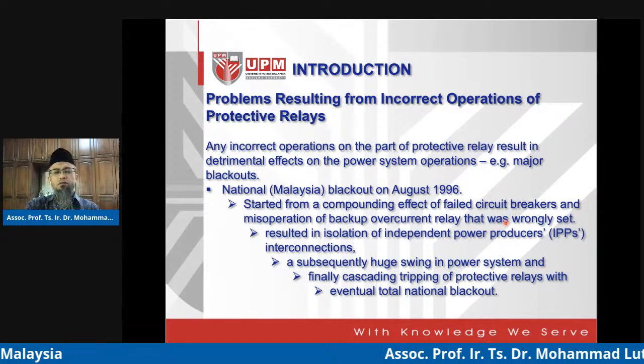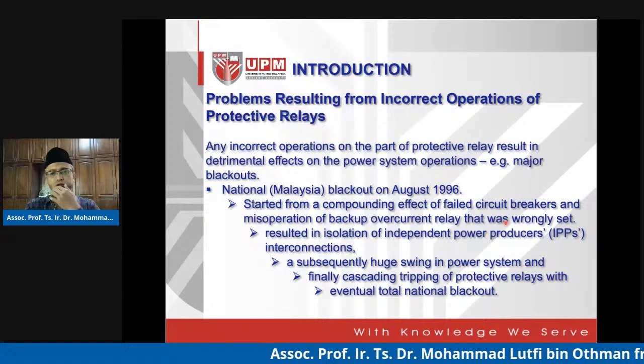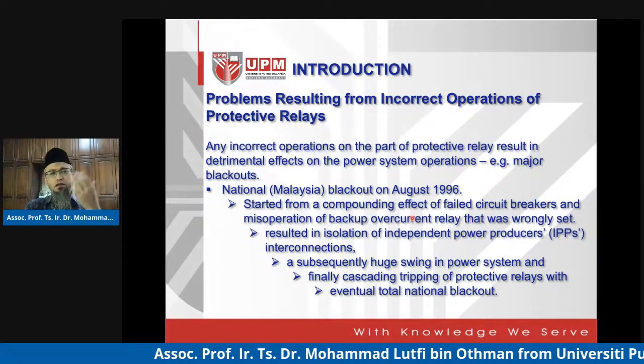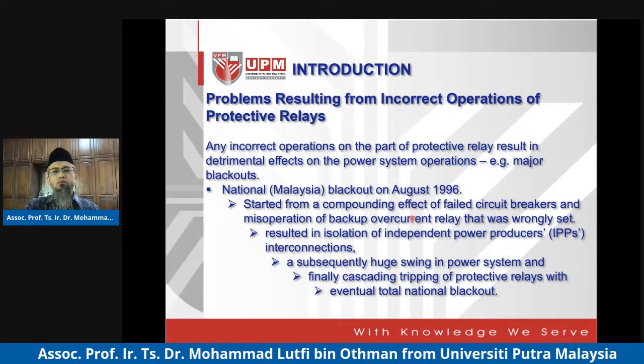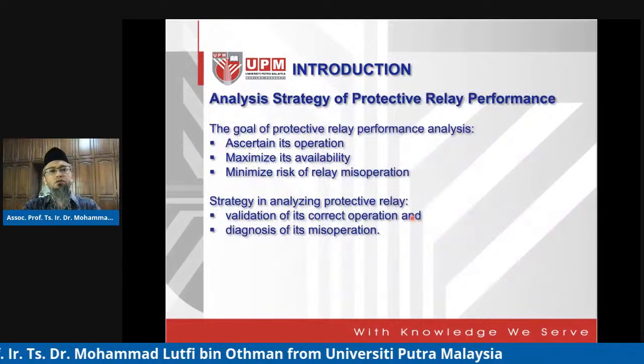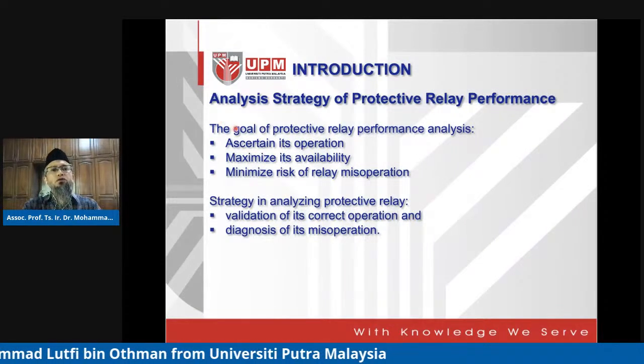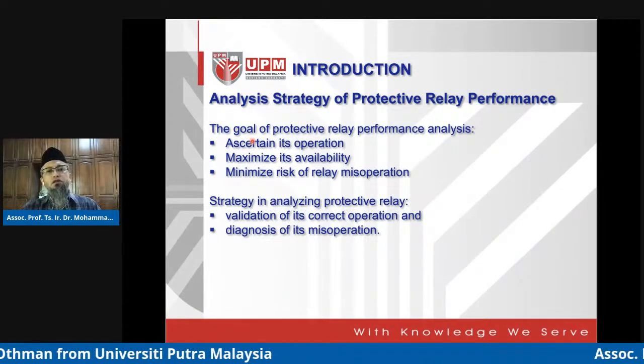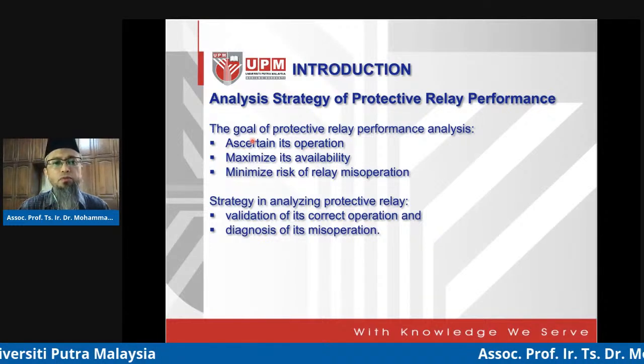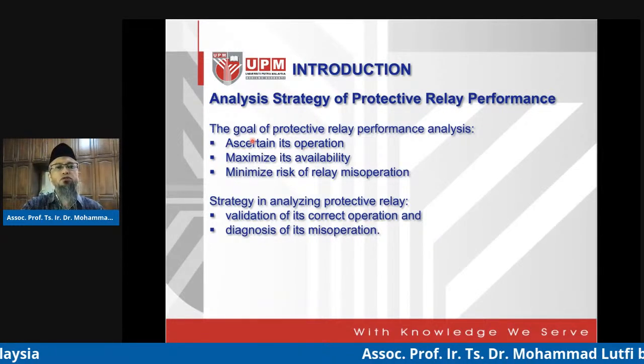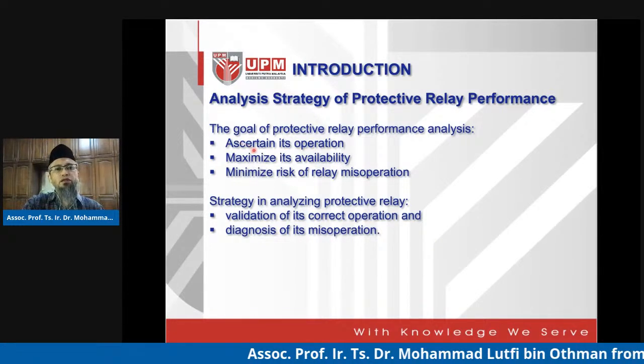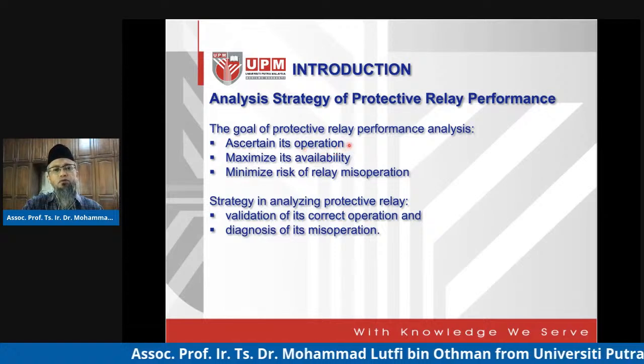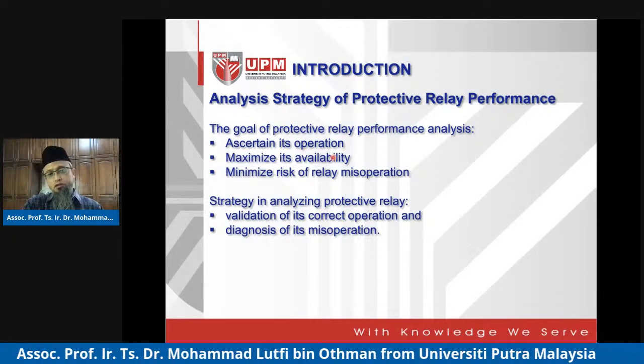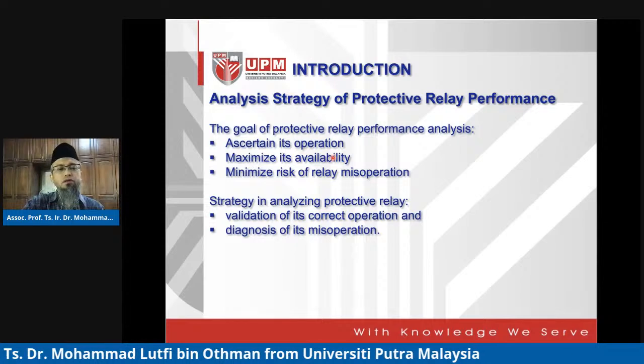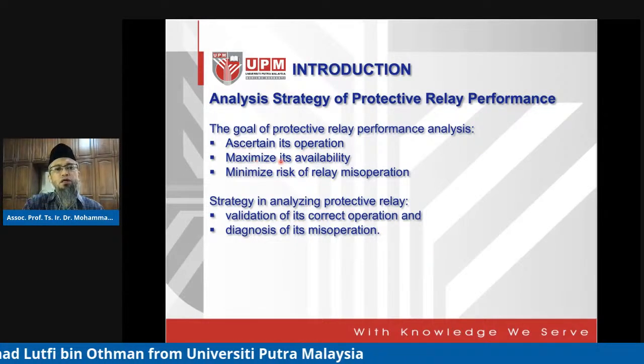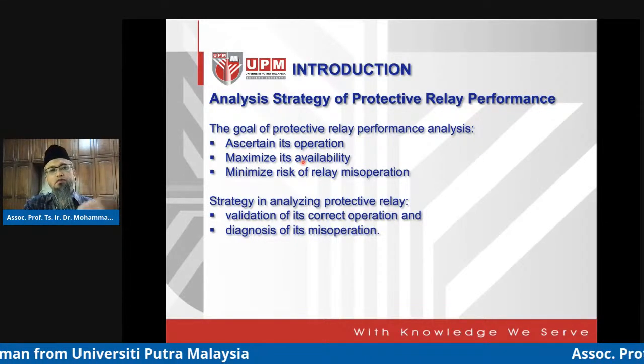So one of the protective devices, we are now looking at a distance relay. Overcurrent relay is just another type of relay, but both are mainly for protecting the power system against faults. So we need to have an analysis strategy for power protection performance. There are goals in doing so. One, we need to ascertain the operation of protective devices or the protection system in a wider aspect. We need to maximize its availability, the protection availability.